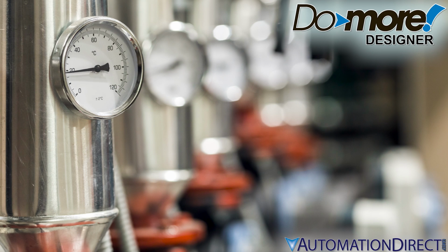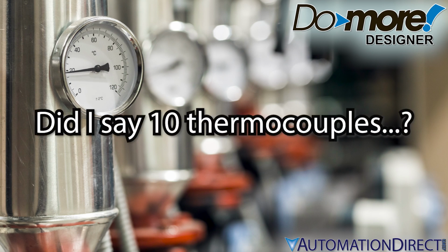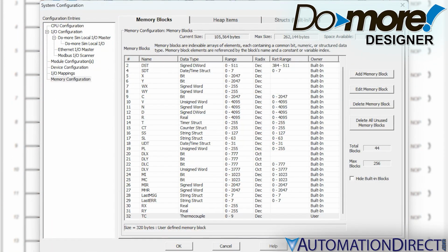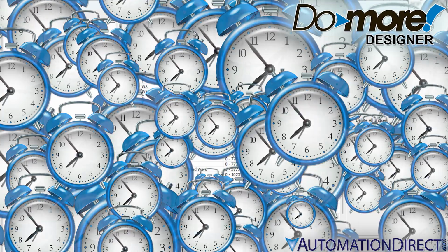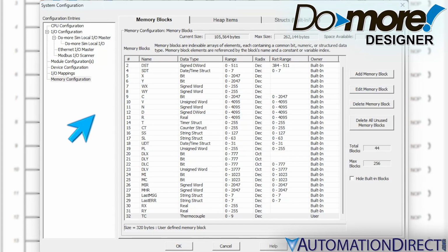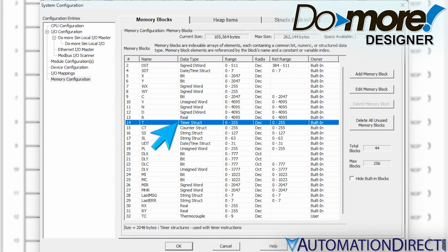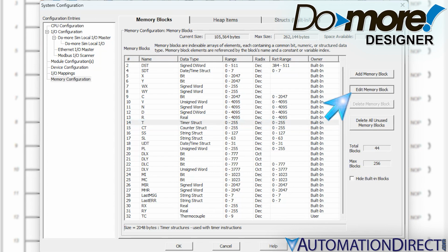What if you get into your project and discover that you're going to have more temperature inputs than you thought? For that matter, what if you are working on a project and you find that the default allocations of the built-in memory blocks don't match your needs? Say you need more timers than the 256 pre-allotted in the Do More memory configuration. You need 400 timers. Well, that would be a lot of timers, but hey, it's your project. To resize memory blocks or make any other changes, highlight the appropriate row and click Edit Memory Block.